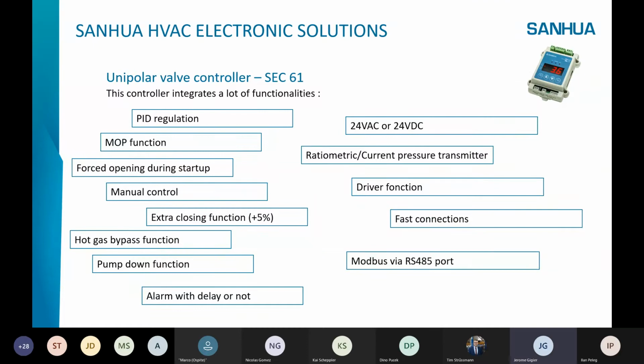The controller integrates a lot of functionality. Inside we have a PID regulation, so you can adjust the PID parameters depending on the behavior of the valve during the test, during the commissioning. We have a MOP function, to control the maximum pressure, like a TXV, a thermostatic expansion valve. We have a forced opening during startup, to avoid the low pressure cutoff. We have also manual control, mainly used during the commissioning or for tests in the lab.